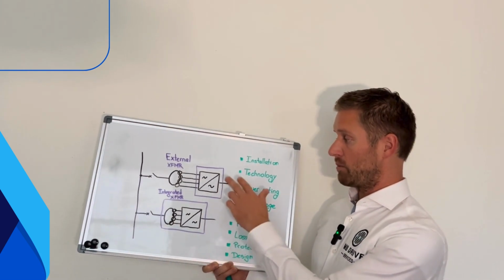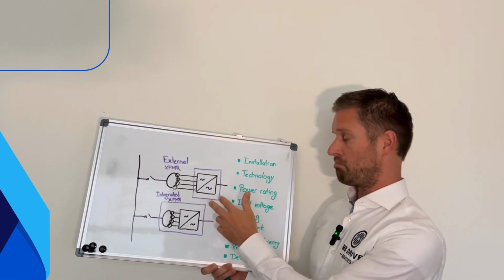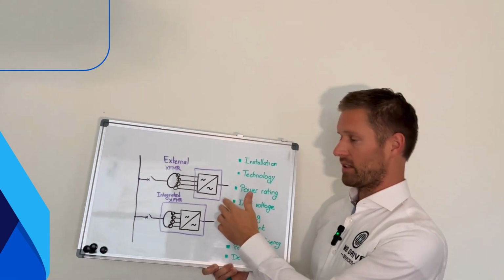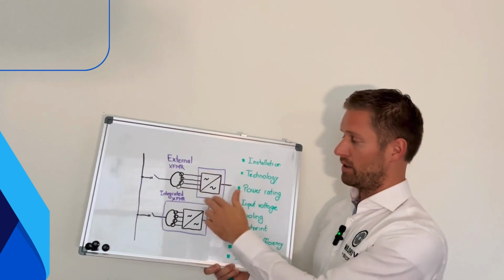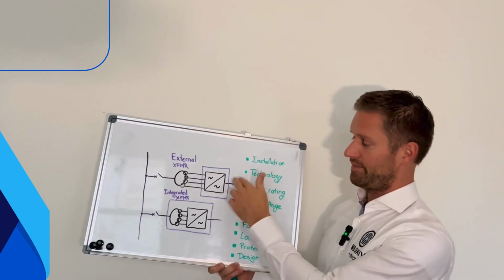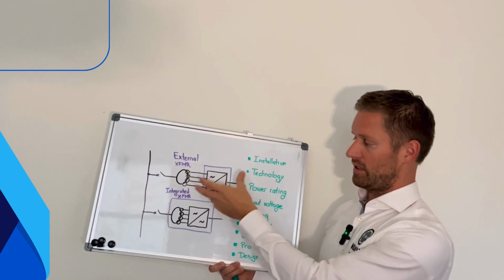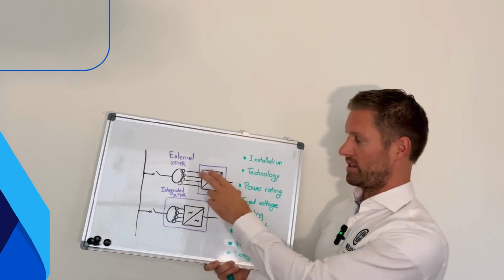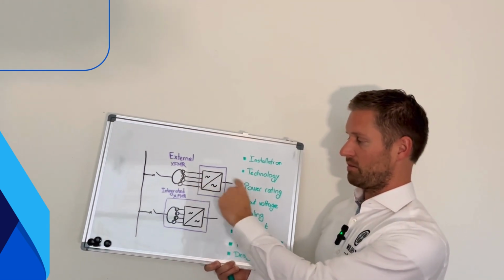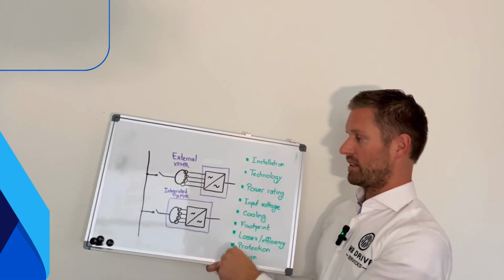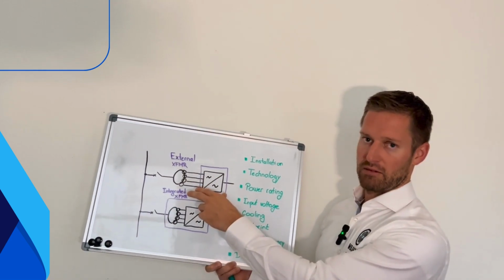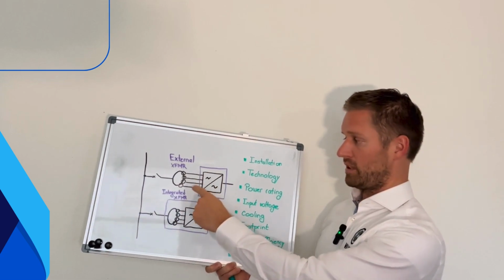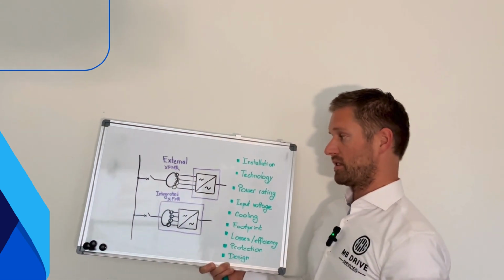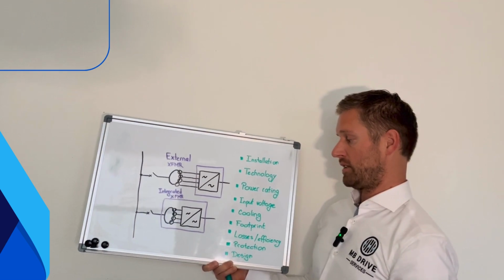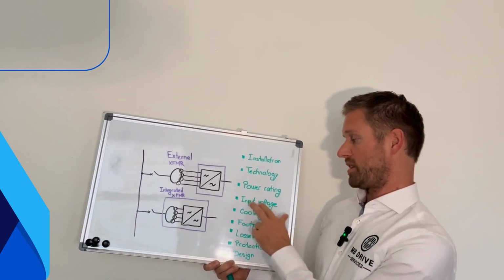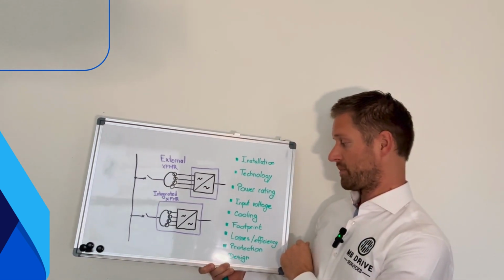There are even power electronic applications, maybe not necessarily drives, but a similar type of converter, not feeding a motor, but playing a role as a static frequency converter, for example 50 to 60 Hz, or in rail applications that have even 220 or 400 kV on the primary of the input transformer. So there is virtually no limitation on the input voltage.